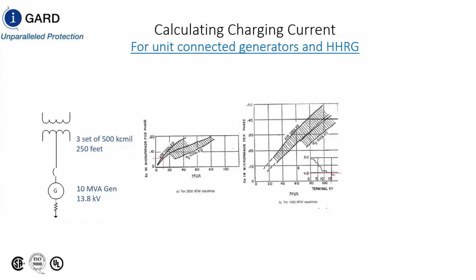So let's look at the generator setup and determine how much charging current we have in the system. Whether it's a unit connected generator or a medium voltage bus connected generator, if you replace this with a circuit breaker, you're looking at the same thing.